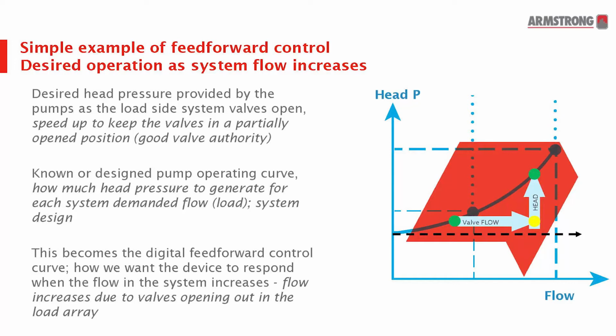So what the intelligent pump will do, it says, I need to get back to that blue control curve, and I will increase my speed to get back on that control curve that's been mapped in my controller by increasing speed and increasing the head pressure, giving the valve its proper authority, giving enough flow, enabling enough head pressure for the flow within the system to satisfy the load at that point of the day.